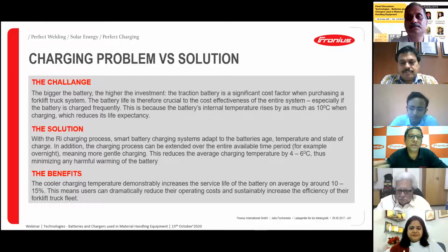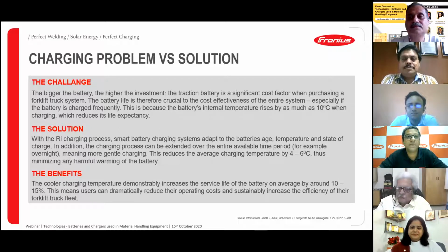At that moment, immediately after discharge, the temperature of the battery is quite high. As per electrical phenomenon, when temperature is high, temperature is equally proportional to resistance. So resistance is the parameter through which you can understand the inner temperature of the battery. And temperature is the only thing in the battery that reduces battery life. That's the biggest criteria.